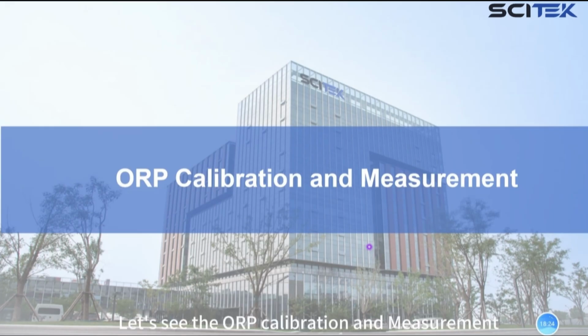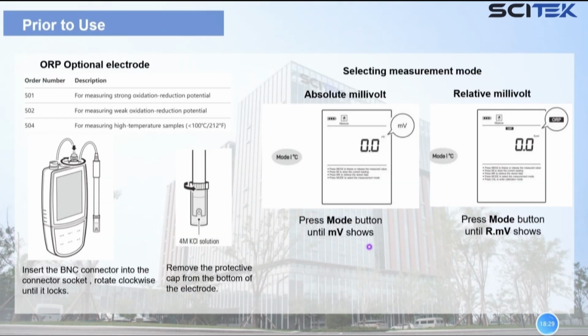Let's see the ORP calibration and measurement. Before using the instrument, a suitable electrode needs to be selected. The 501 is used to measure strong oxidation reduction potential. The 502 is used to measure weak oxidation reduction potential. The 504 is used to measure high temperature samples.